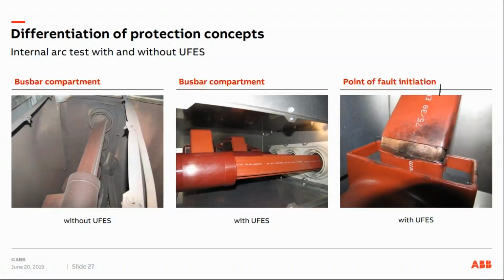What we can see here is some pictures and the impact of an internal arc without the UFES and with the UFES. Without the UFES, you can see clear signs of the arc fault on the left-hand side, in your panel and inside and outside your panel. Whereas with the UFES in the busbar compartment, there are no signs. There's just a footprint visible at the point of fault initiation of the arc fault. So as you can see, the damage is much more reduced compared to the application without the UFES.